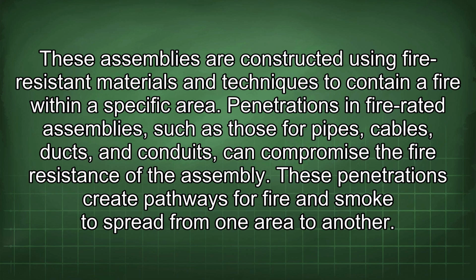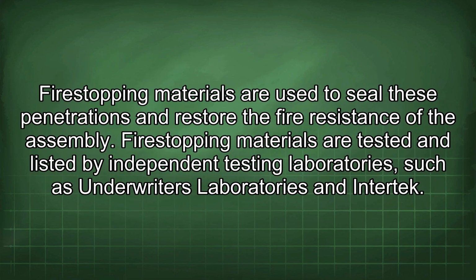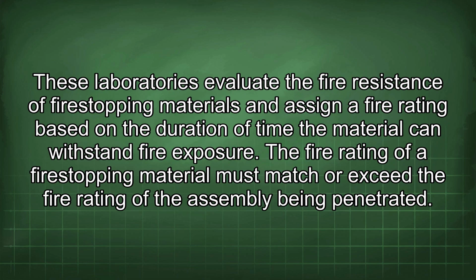Penetrations in fire-rated assemblies, such as those for pipes, cables, ducts, and conduits, can compromise the fire resistance of the assembly. These penetrations create pathways for fire and smoke to spread from one area to another. Fire-stopping materials are used to seal these penetrations and restore the fire resistance of the assembly. Fire-stopping materials are tested and listed by independent testing laboratories such as Underwriters Laboratories and Intertek. These laboratories evaluate the fire resistance of fire-stopping materials and assign a fire rating based on the duration of time the material can withstand fire exposure. The fire rating of a fire-stopping material must match or exceed the fire rating of the assembly being penetrated.